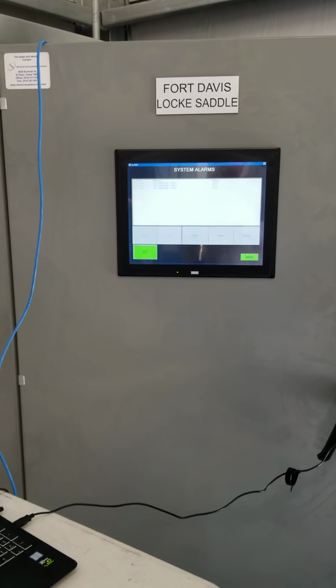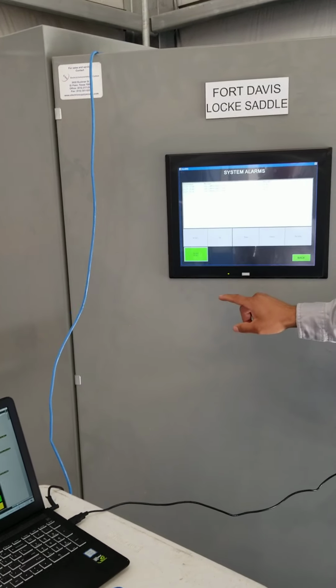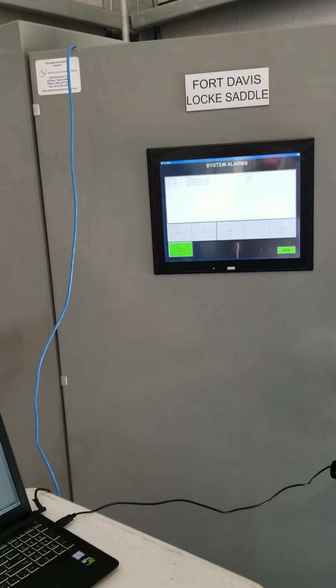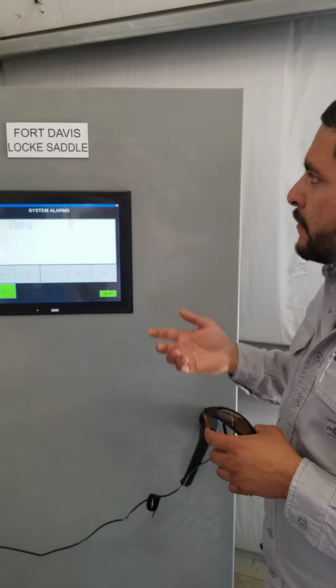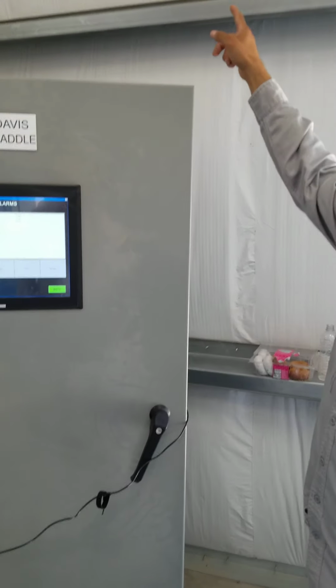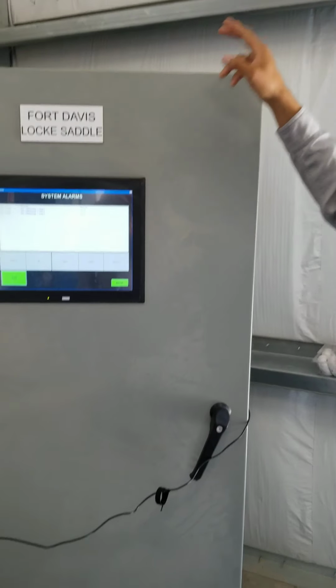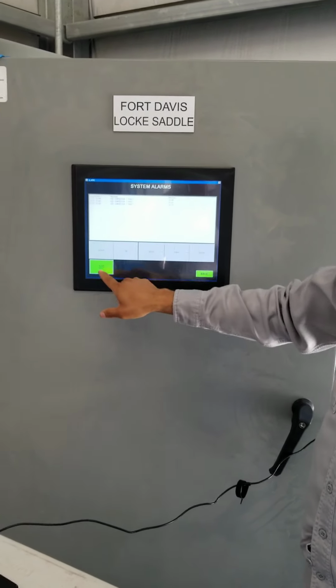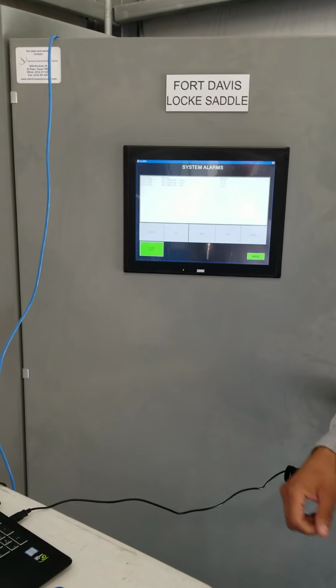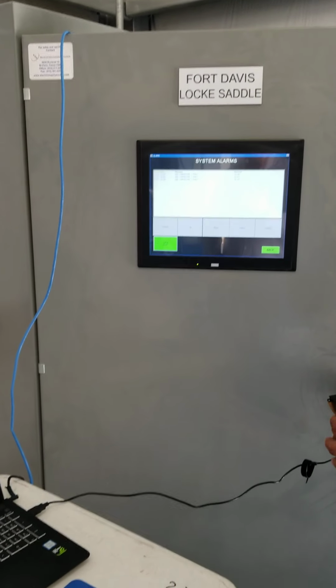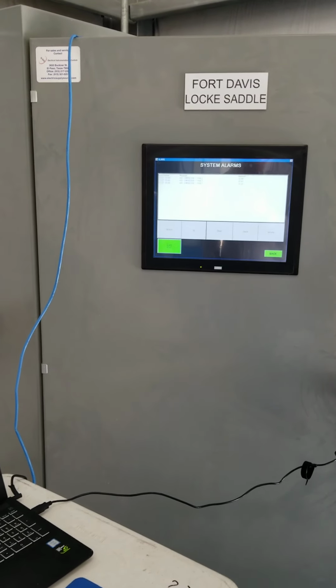And the only way to acknowledge these currently is to come in here physically. Yes, any alarm will be active, and then it's gonna sound your buzzer and your beacon light, and then the operator will need to come here and press alarm reset, and then fix the problem. So that's a very simple alarm page.